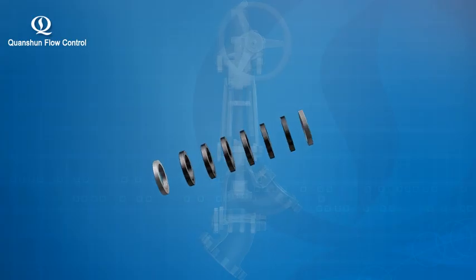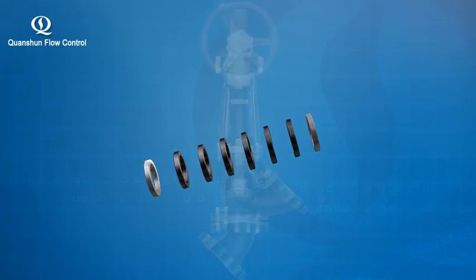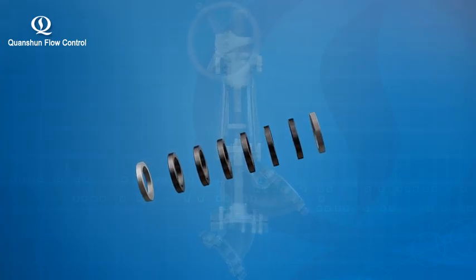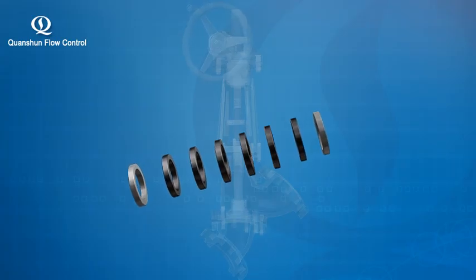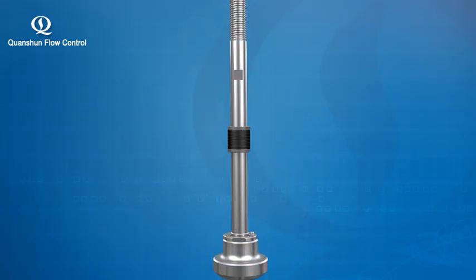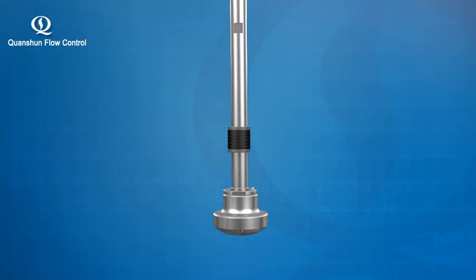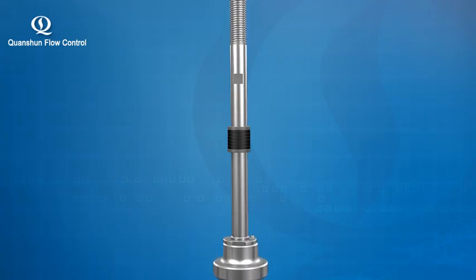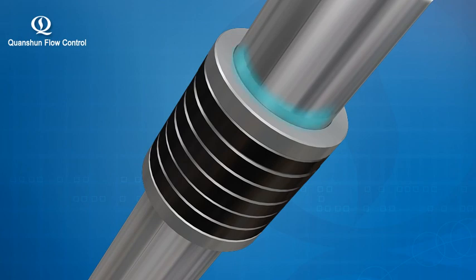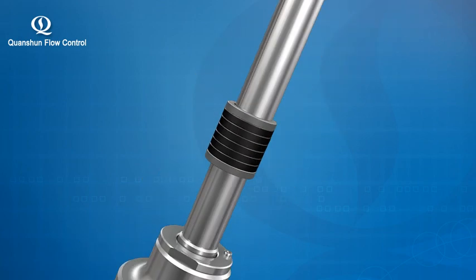6. Stem packing. With a braided graphite wrapping the upper and lower positions respectively in 2 round turns and flexible graphite form in between. This design guarantees the sealing strength of both the packing and the stem and gets rid of the graphite powder attached to the stem effectively during stem motion.